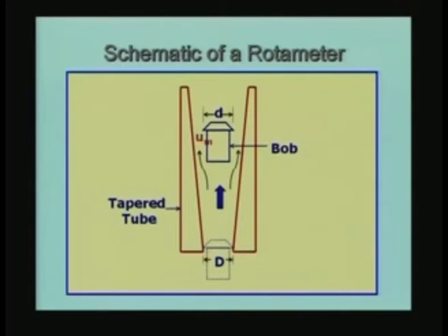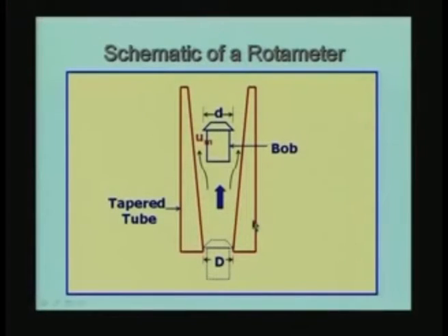In the case of the three measuring meters which we talked about, the venturi, the nozzle and the orifice plate, normally we use the horizontal orientation. The meter will be located horizontally in the pipeline, and many times the pipeline is actually horizontal, and therefore it does not involve any problem. But if you are going to install a rotameter, you have to make an arrangement such that locally the flow direction is exactly vertical from bottom to up. It should be from bottom to top. The flow direction is fixed from the bottom to top against the gravity. Very important to remember.